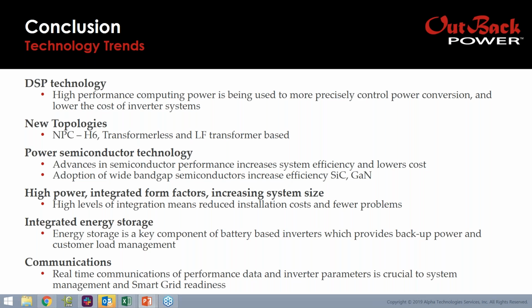Also, real-time communication of performance data and inverter parameters is crucial to managing large inverter systems and for smart grid readiness. It's a sophisticated scheme of communications, both internet and Ethernet connected, along with some Modbus protocols with SunSpec, which allow inverters to be controlled with the same set of commands regardless of manufacturer. That's pretty important.